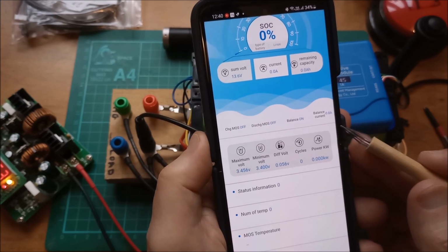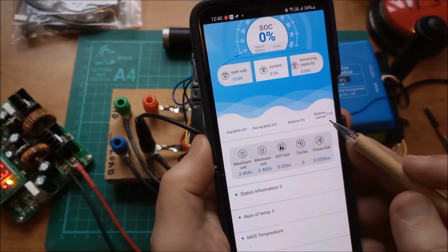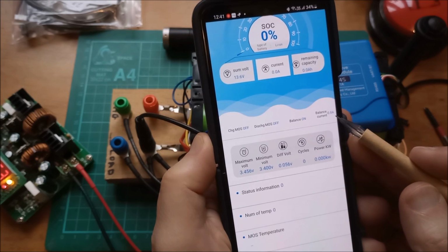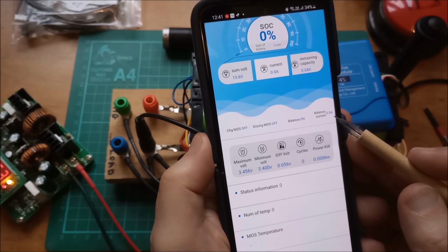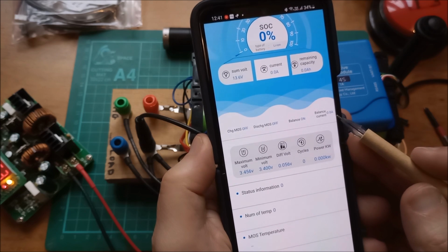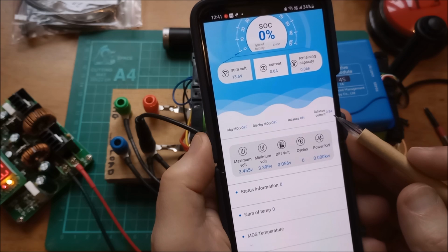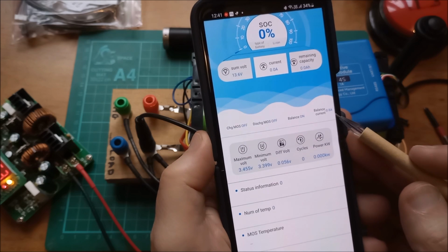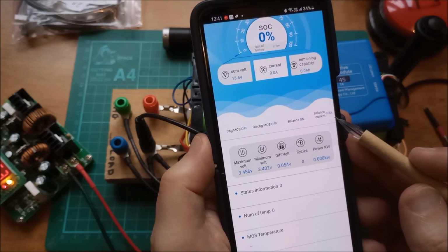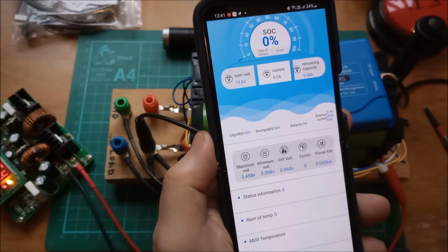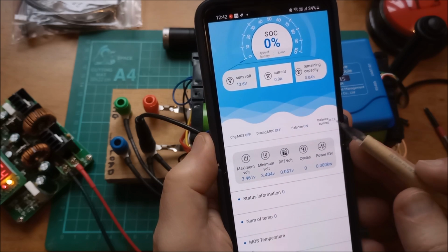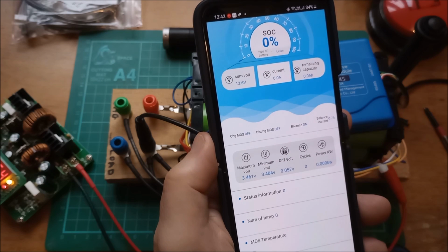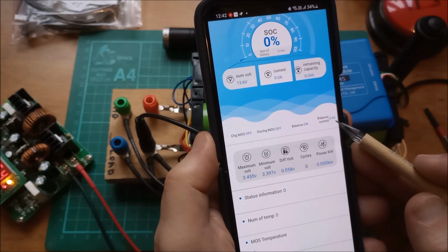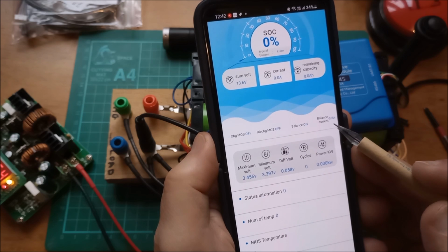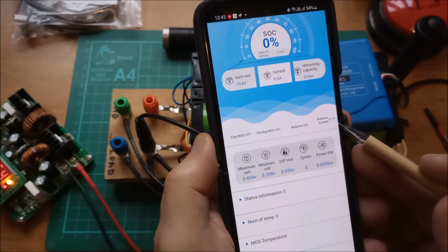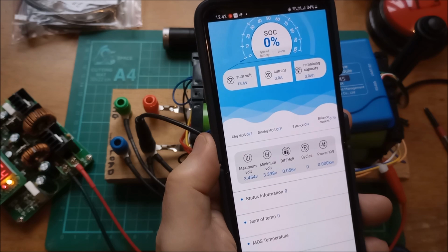And there are some really weird anomalies. It shows the balance current currently as minus 0.8 amps, and this seems to go in tenths of an amp, so 100 milliamp increments or decrements. But when it shows minus 0.9 amps, it does something really bizarre. I'll try and capture it on camera. Yeah, there it is. It's minus 0.900000004. So there's some sort of bizarre calculation, rounding error when it shows 0.9 amps. 0.7 and 0.8 are fine, but 0.9 has this very strange extra digits on the end.